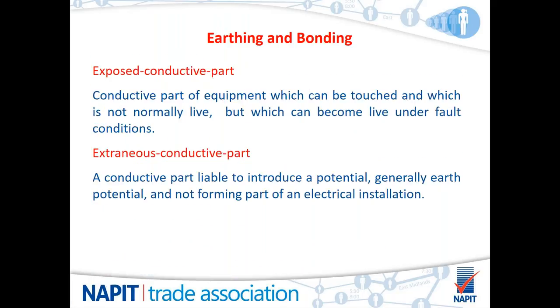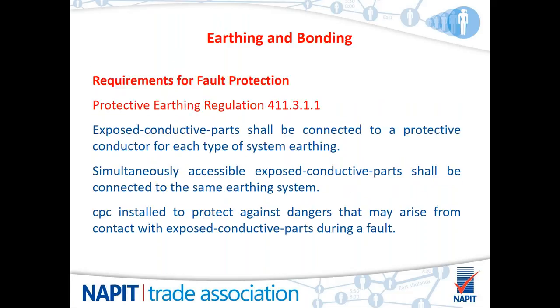Two more terminology references: the difference between exposed conductive parts and extraneous conductive parts. An exposed conductive part is a conductive part of the equipment that can be touched and is not normally live, but which can become live under fault conditions, such as the outside of a metal kettle, the front of a storage heater, or a Class 1 metal light fitting. These are all parts of the electrical system that could become live under fault conditions. An extraneous conductive part is a part not forming part of the electrical installation that normally introduces a potential, generally earth potential, 0 volts. Examples are water pipes, gas pipes, etc.